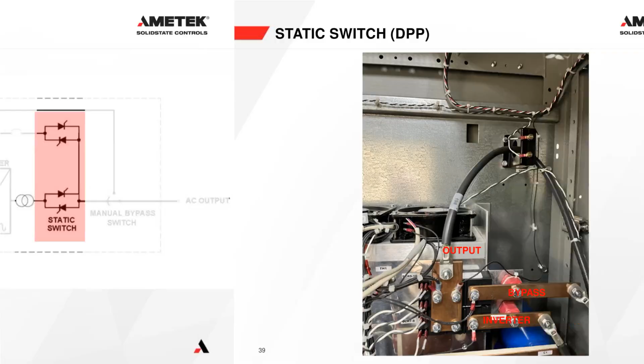So once again, think about it just like a switch. We have a switch here, and a switch here. Through either the push buttons on the front of the UPS or automatically through our sensing circuits, we can choose either the inverter to load or the bypass to load. What the UPS does, as per its design, is everything it can to keep the inverter on load at all times, because that's connected to the DC bus and the battery and creates a beautiful sine wave and isolates you from any sags or power fluctuations on your bypass. So we always want to keep it on inverter as much as we possibly can.